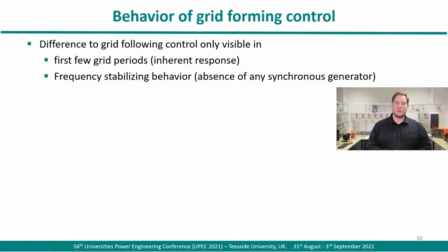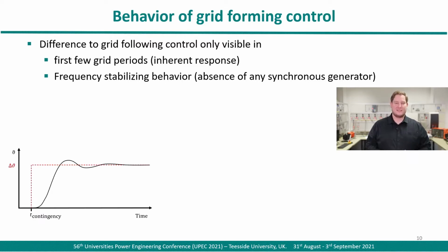The grid following control will provide its referenced currents. The grid forming control will swing around the operation point and provide supporting currents. Clearly, grid following control could be tuned in such a way that it will behave somehow the same after a few grid periods. But with total absence of synchronous generator, it will easily drift away. When the contingency happens, or at a simple grid impedance or angle change, the grid forming control will react a little inert to provide the emulated mass. Due to the synchronizing behavior, it will change its output angle, and because of the damping, it will become stable.